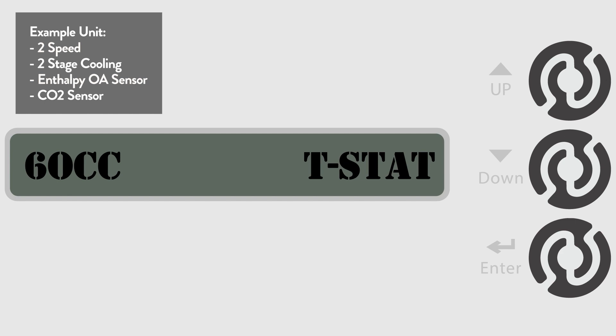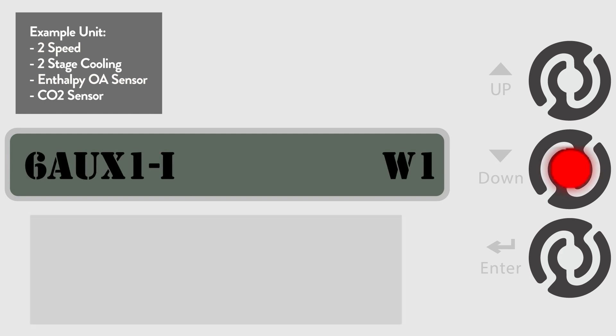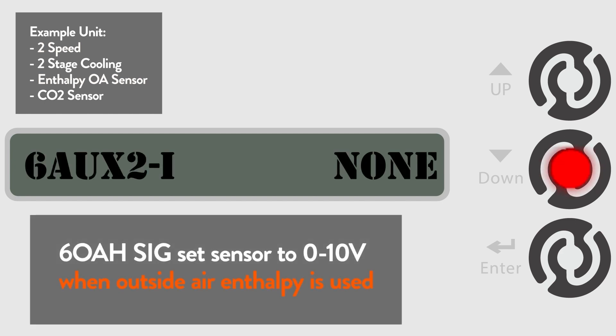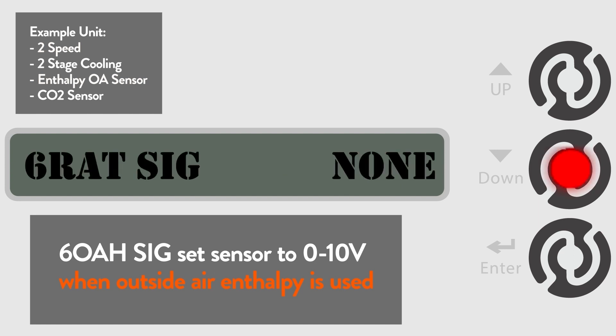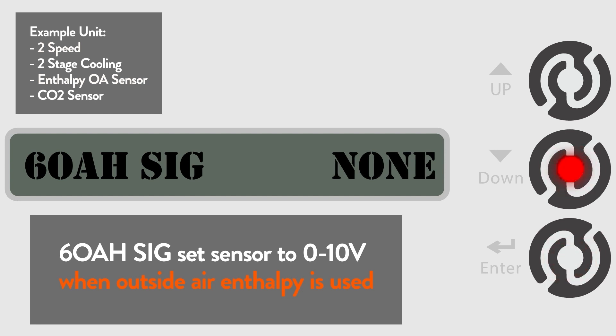Since the controller default assumes a dry bulb temperature sensor, we will have to activate the outside air humidity to get an enthalpy reading. Go to the 6 OAH SIG menu. The default is none, but for this example we are using an outside air enthalpy and will need to change the default setting for outside air humidity to 0 to 10 volts.